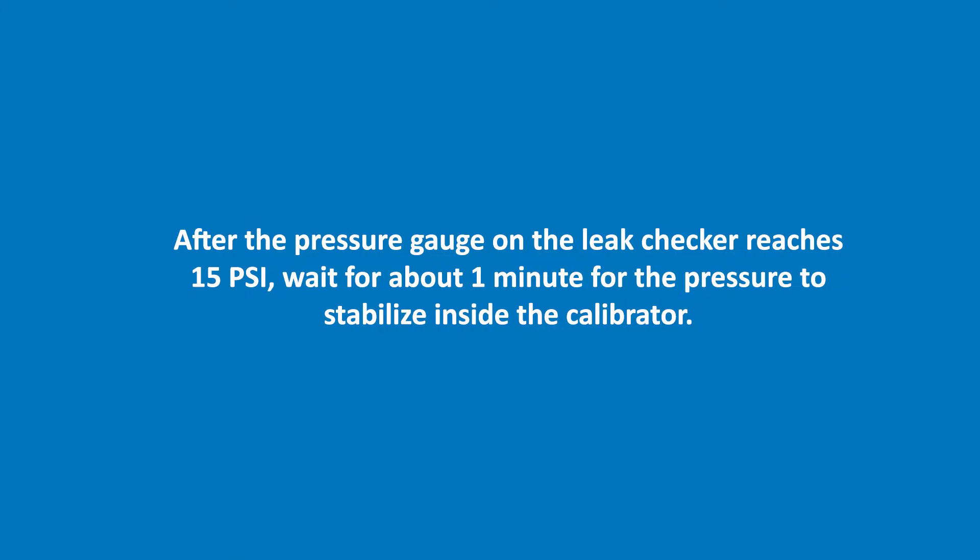After the pressure gauge on the leak checker reaches 15 psi, wait for about one minute for the pressure to stabilize inside the calibrator.